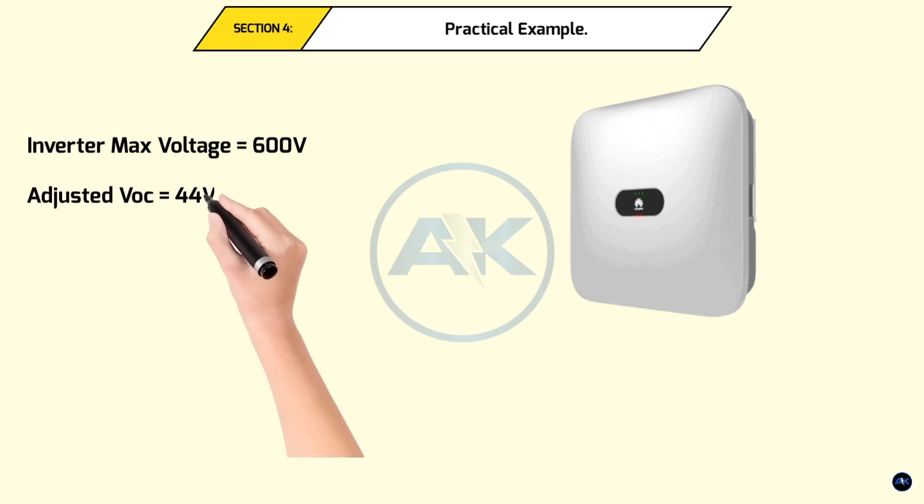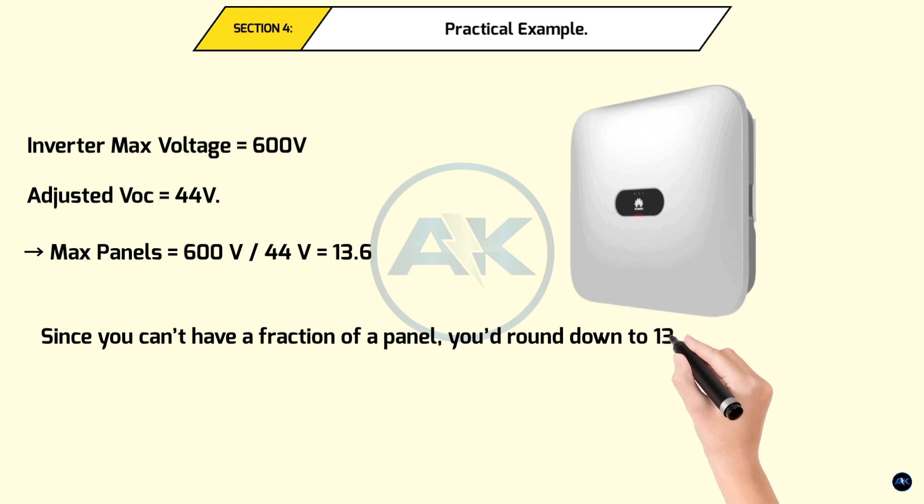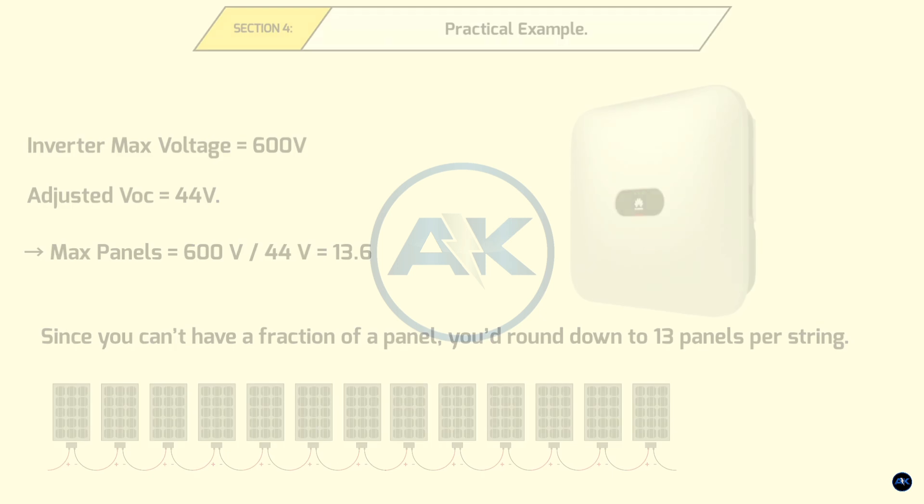Section 4. Practical Example. Let's say you have an inverter with a maximum input voltage of 600 volts and panels with an adjusted VOC of 44 volts. Dividing 600 by 44 gives you about 13.6. Since you can't have a fraction of a panel, you'd round down to 13 panels per string. Remember, it's always better to stay under the inverter's limit to account for any unexpected voltage spikes.